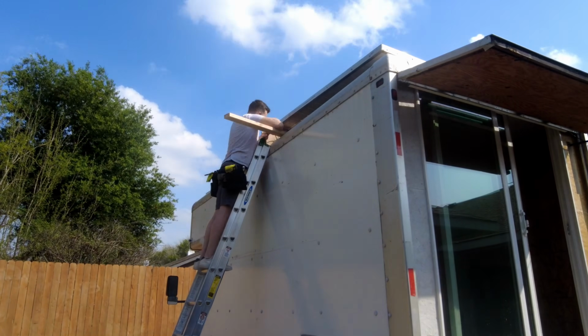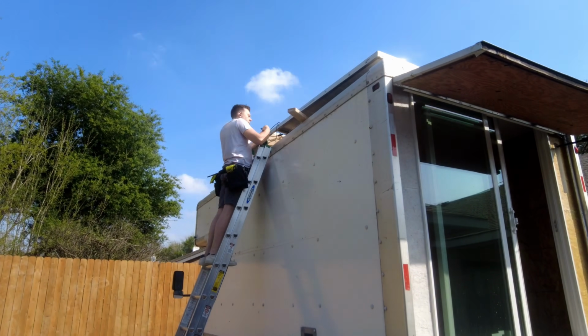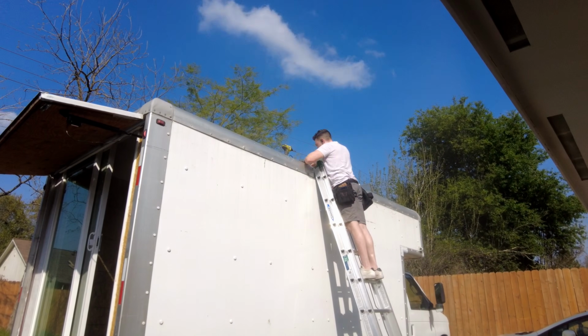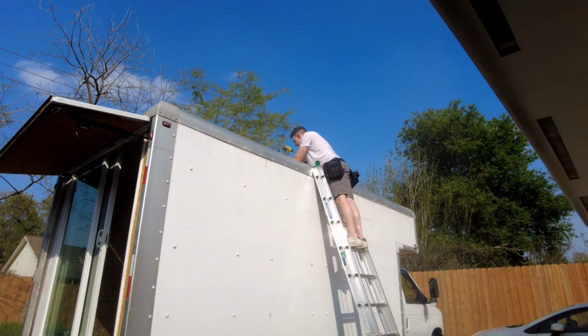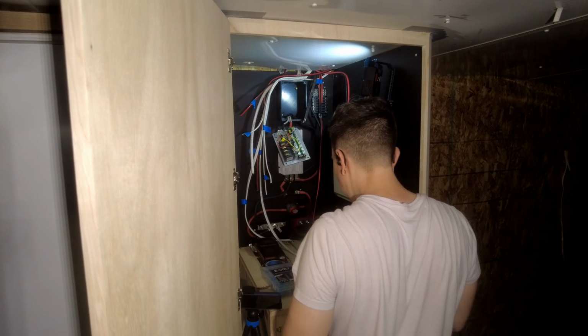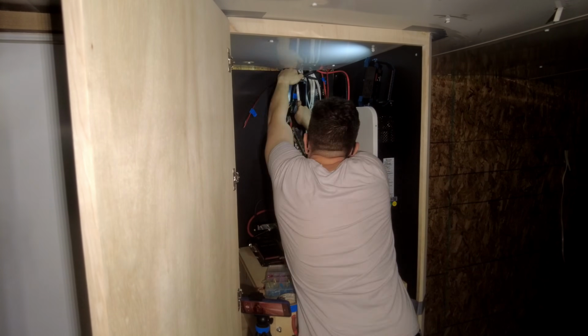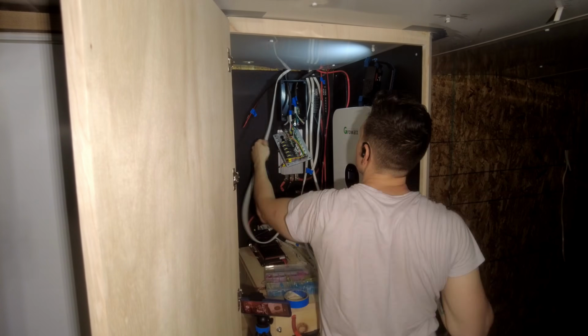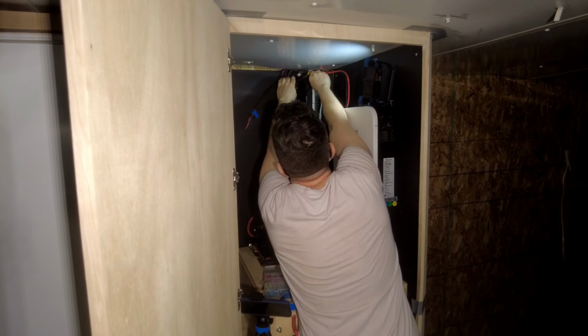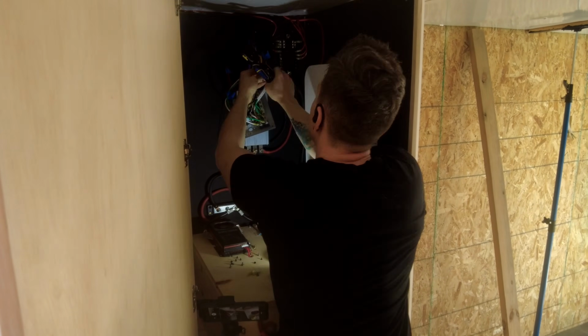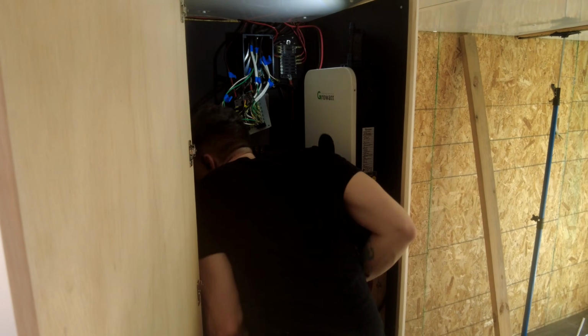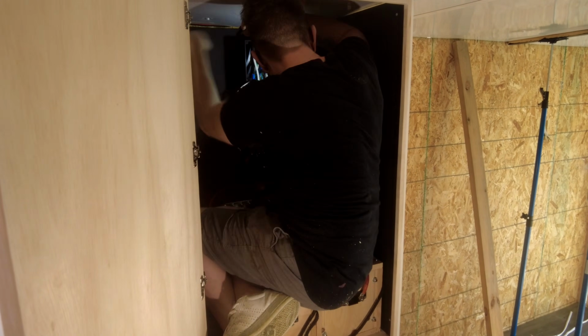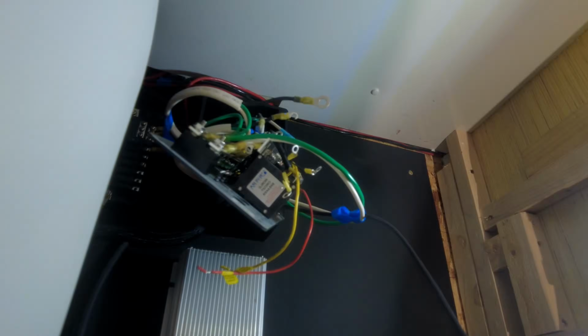With the solar panel wiring done on the inside, I went to the roof to finish up the series parallel connections and then clean up the routing of the cables up there. After that, I finally got to tear apart these nasty 110 cables that have been hanging from the ceiling, breaking them into their individual components of load, ground, and neutral, and connecting those to our 110 breaker panel box and their corresponding breakers.